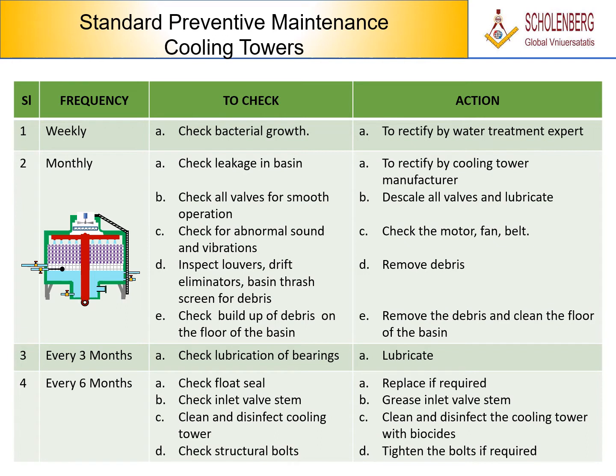4. Frequency: every 6 months. To check: A. Check float seal. Action: replace if required. B. Check inlet valve stem. Action: grease inlet valve stem. C. Clean and disinfect cooling tower. Action: clean and disinfect the cooling tower with biocides. D. Check structural bolts. Tighten the bolts if required.